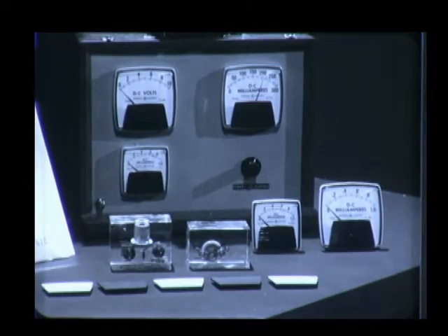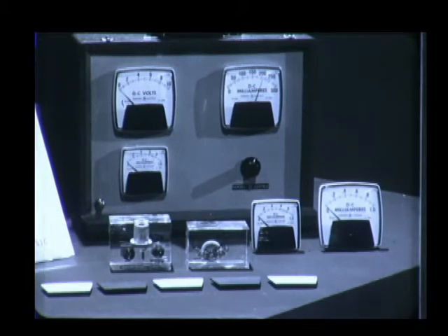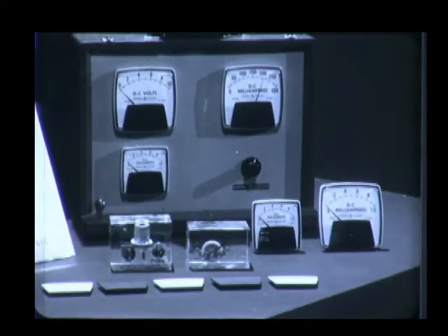The core magnet movement has conventional control springs and requires a zero set, which is completely sealed with a neoprene O-ring. The self-shielding of all DC movements in these instruments allows them to be mounted on magnetic and non-magnetic panels without special calibration, cluster mounting bezel to bezel without interaction, and the effects of stray magnetic fields are minimized.